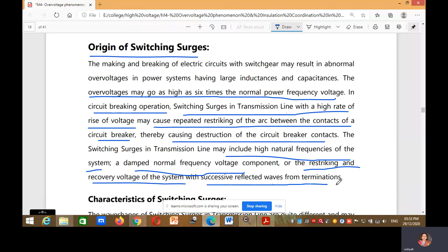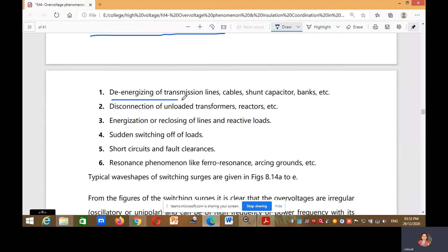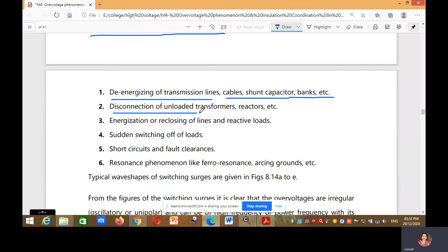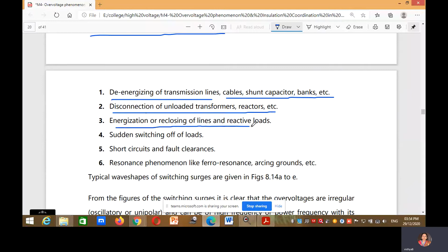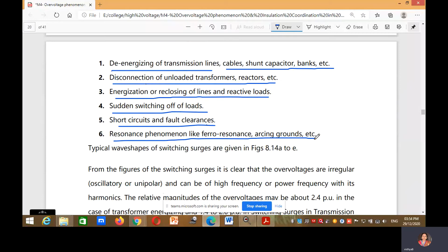Next is the characteristics of switching surges. The wave shapes of switching surges in transmission line are quite different and may have origin from any of the following sources. First is de-energizing of transmission lines, cables, shunt capacitor banks, etc. Next is disconnection of unloaded transformers, reactors, etc. Energization or reclosing of lines and reactive loads. Next is sudden switching off of loads, short circuit and fault clearances, resonance phenomena like ferro resonance, arcing grounds, etc.